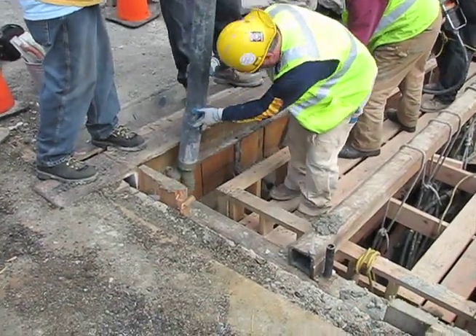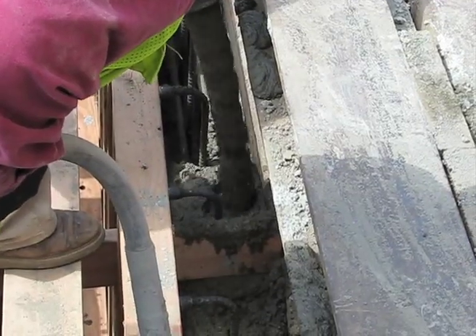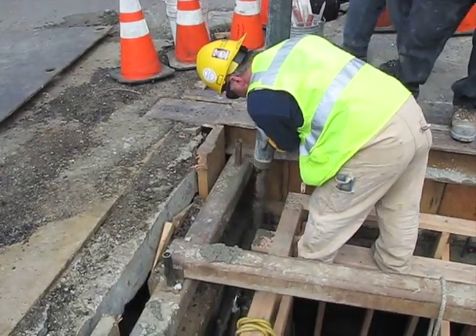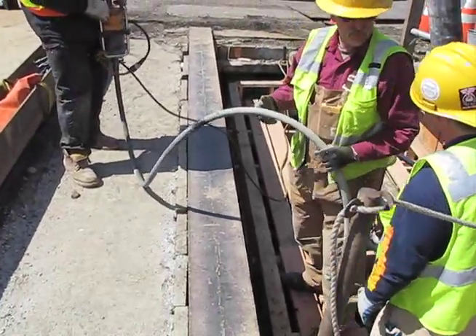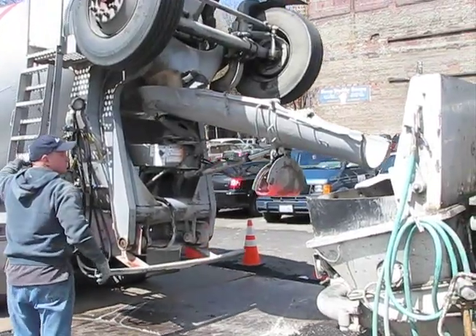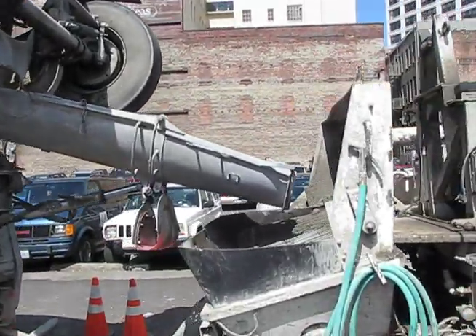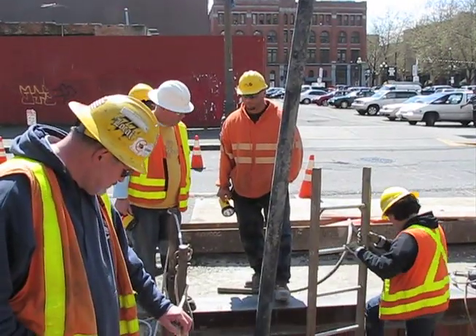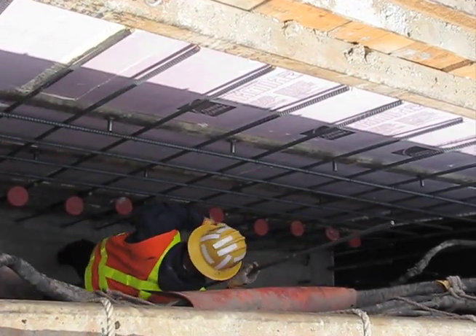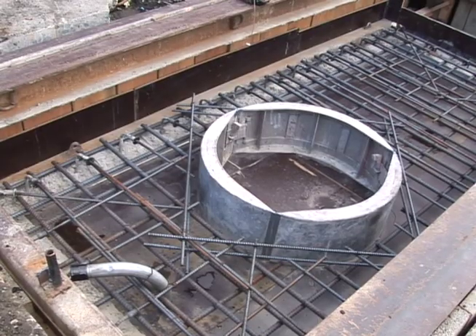Concrete is poured in stages. First the floor, then the walls, and finally the top. Each stage with an interval of curing time. The vault being replaced here was installed about 60 years ago. So these vaults have to last a long time and withstand the constant pounding of traffic traveling overhead. Finally, the cable splicers will make the connections for junctions of wires that travel through the conduit to the next vault. The downtown network is a grid of wires attached to transformers throughout the downtown area.